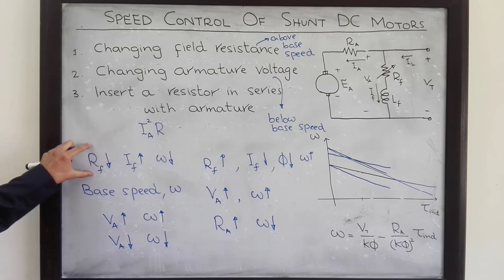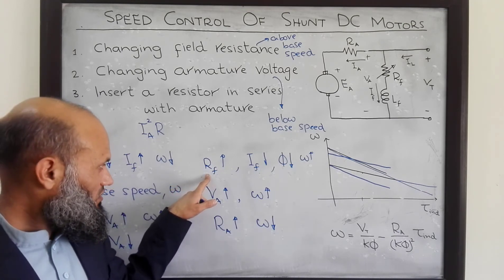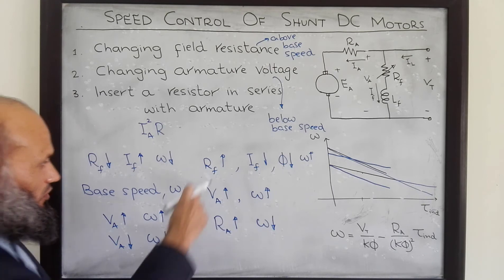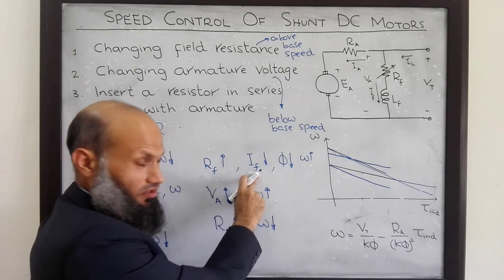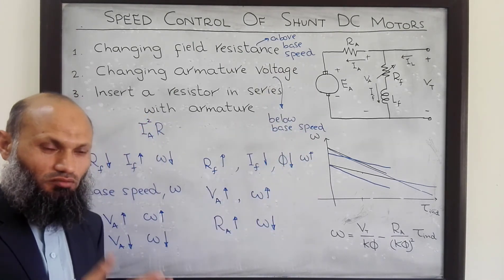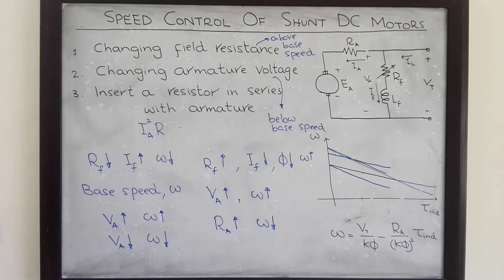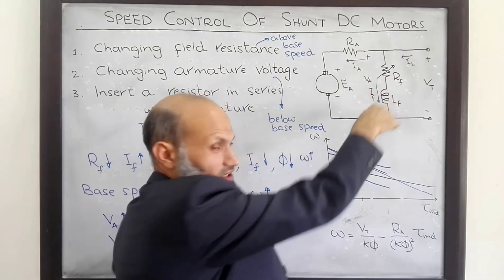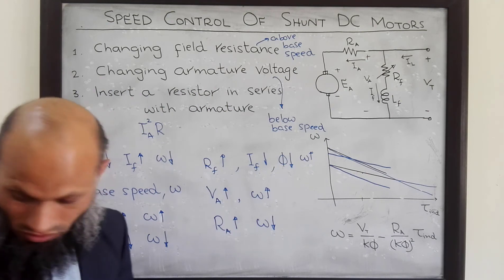One more important point: increasing field resistance is not problematic since current gets smaller and smaller. However, if we increase it to an excessive amount, the speed will become greater and greater and can damage the motor mechanically — at very high speed the motor may get damaged. For example, if due to some reason there is an open circuit in the field circuit connection, let's consider what will happen in that situation.